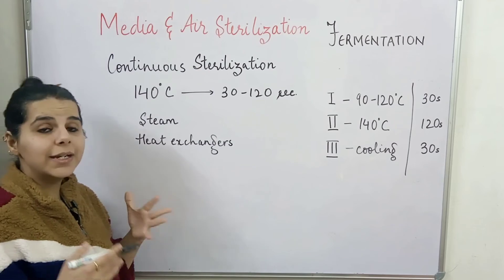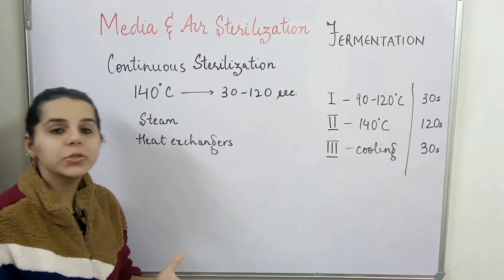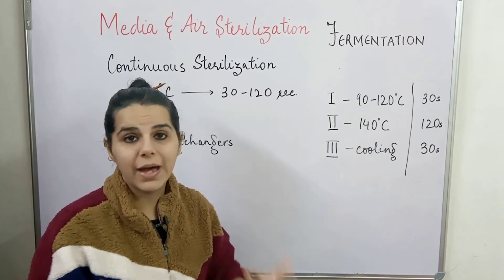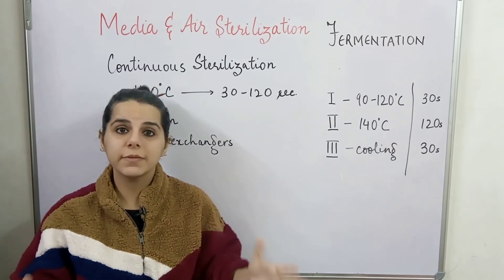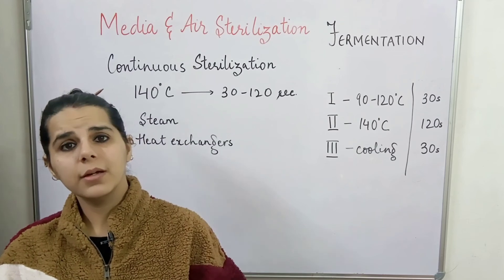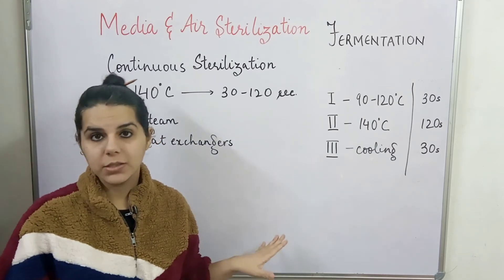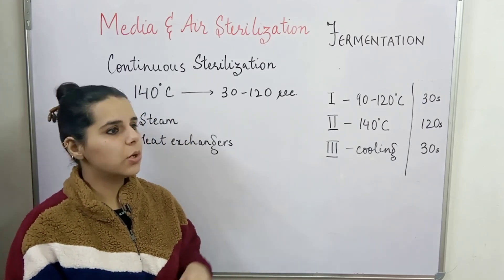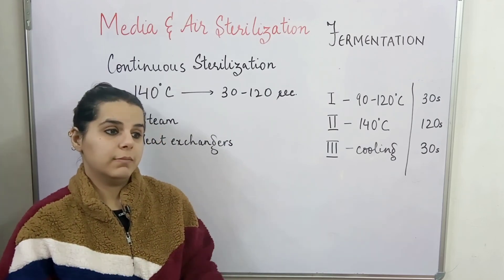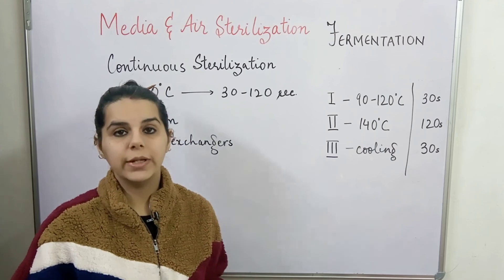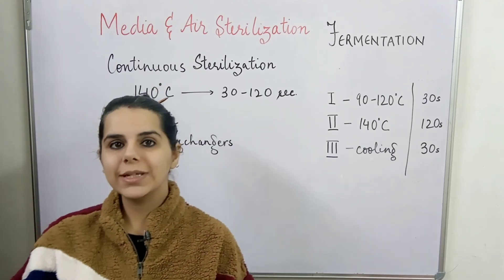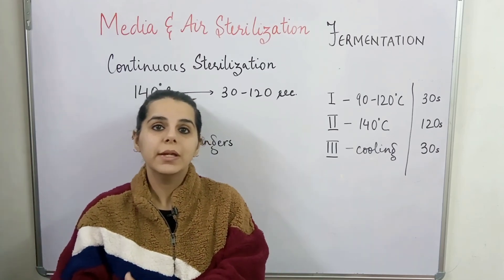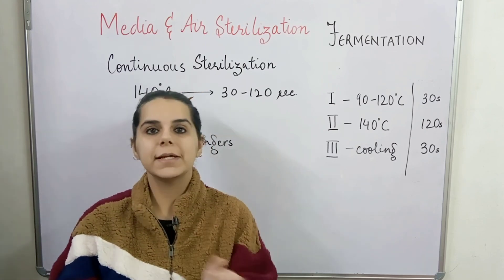One major advantage of continuous sterilization is that 80 to 90 percent of the energy is conserved, since there are no batches and the sterilization time is very short. However, a disadvantage is that due to rapid temperature fluctuations — heating followed by instant cooling — certain components precipitate out, such as calcium, which precipitates as calcium oxalate.